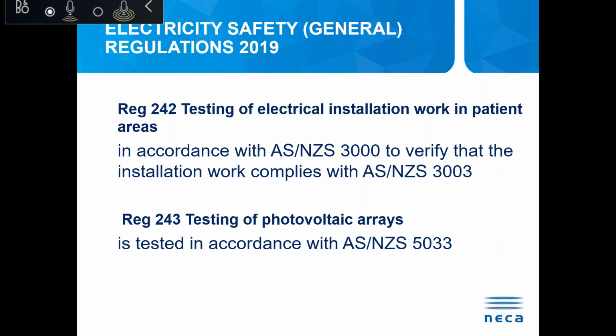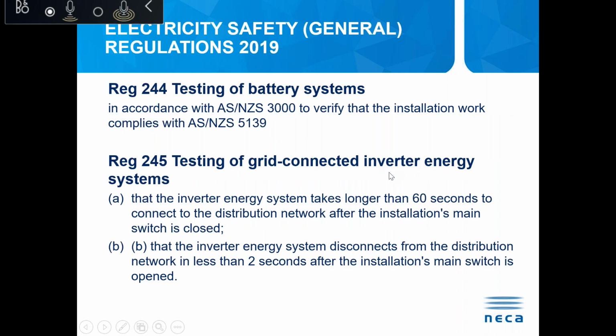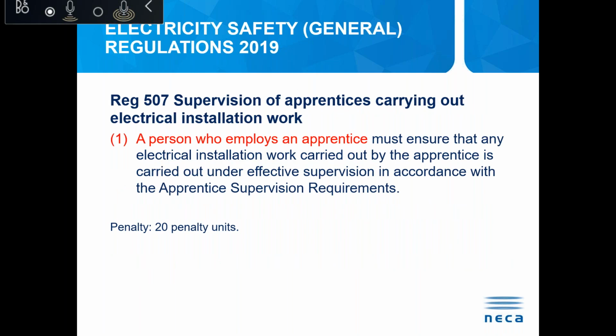The general regulations also call up specific standards. So they're called up not just in the wiring rules now, they're also called up in legislation. So 3003 for medical patient areas, 5033 for photovoltaic arrays. Testing of battery systems is now called up in the new standard, AS/NZS 5139. Testing of grid connected inverter systems, and they've actually specified the anti-islanding requirements. So this is now called up in legislation, not just by the standards.